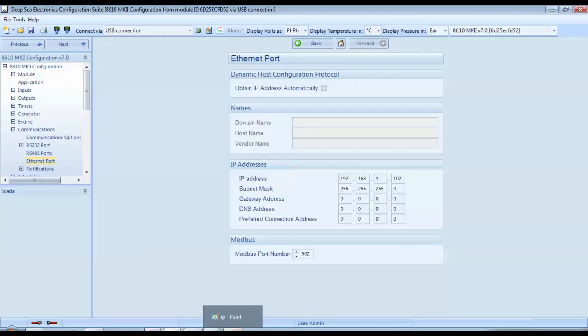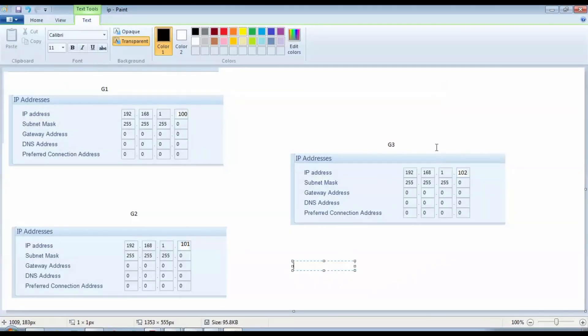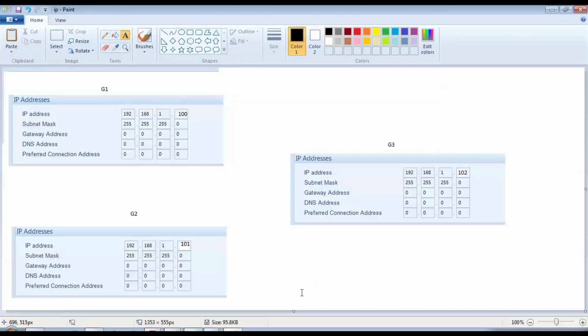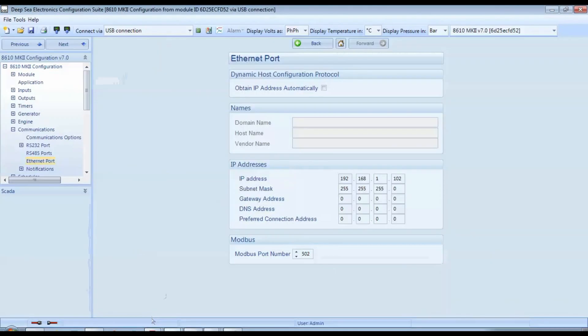Click 'Write to Controller' to save settings. Repeat the same procedure for other controllers — for example, generator number 2: IP 192.168.1.101. After writing parameters, you must disconnect the DC supply of the controller; otherwise, the IP address will not be saved into memory. After resetting DC power, you can confirm the new IP address in the controller's communication page. Verify the IP addresses in each controller's display.